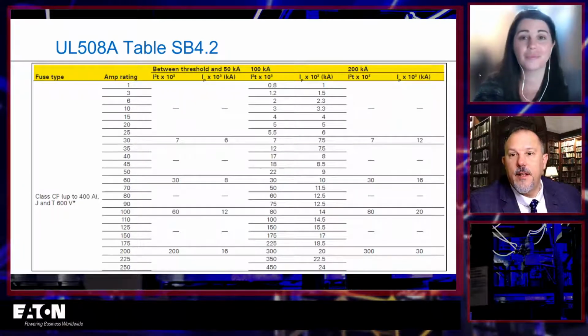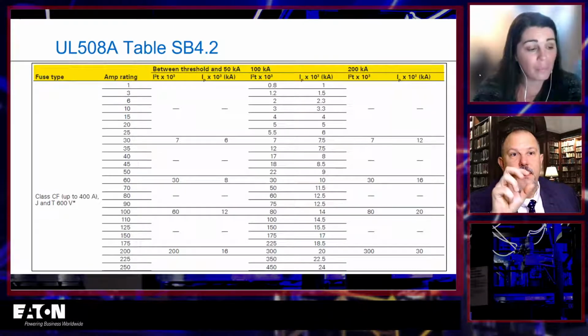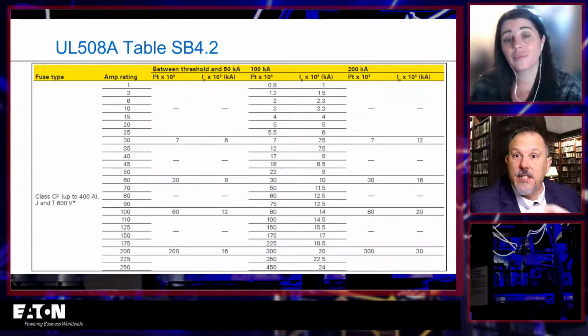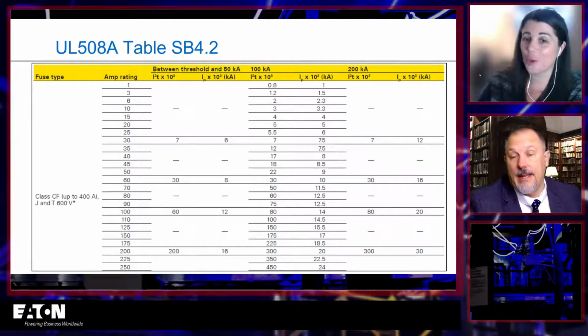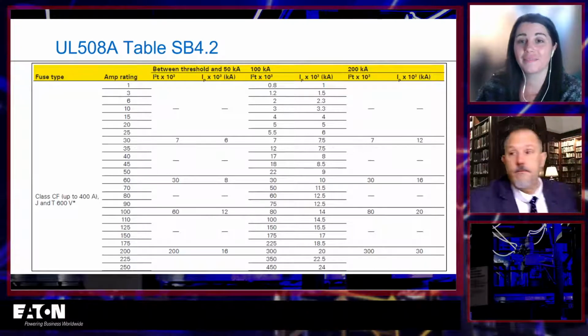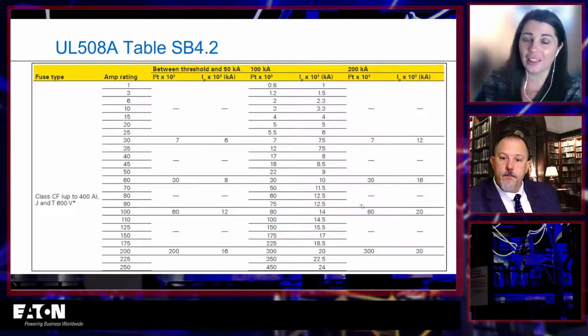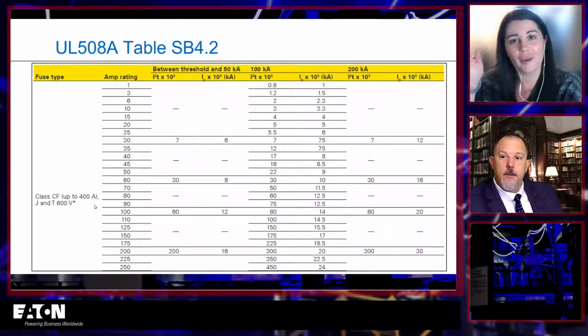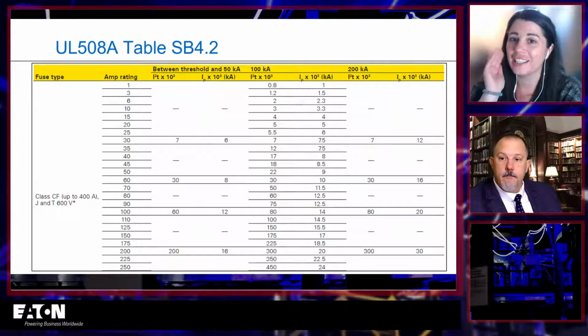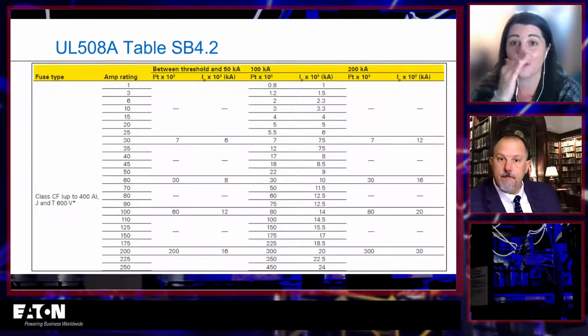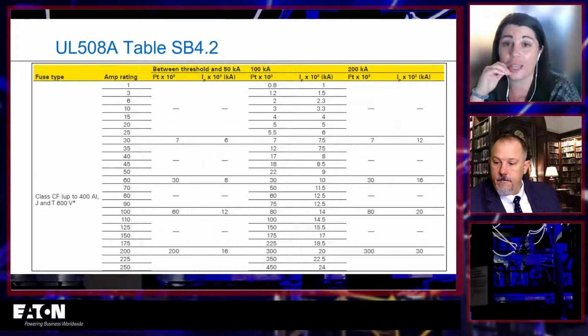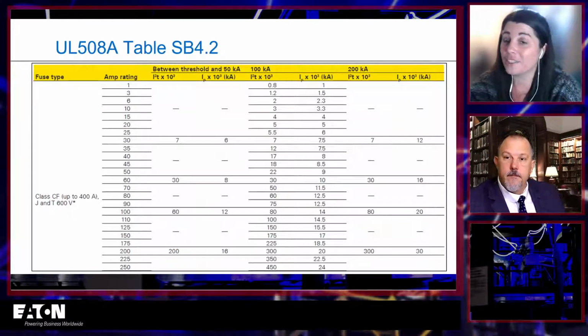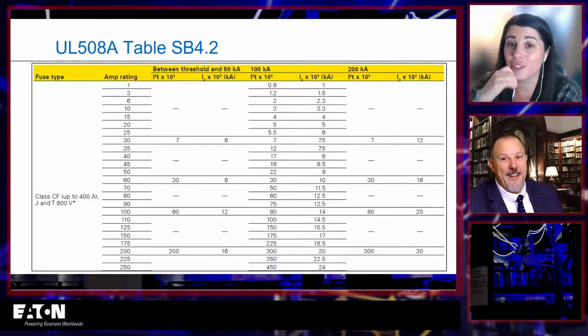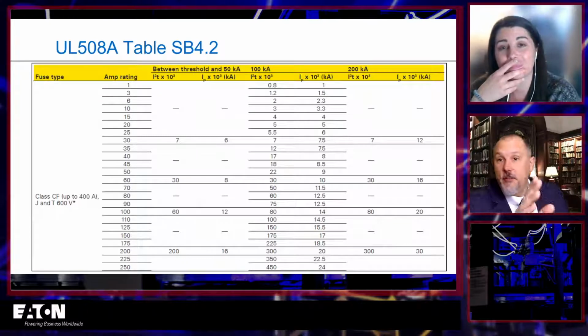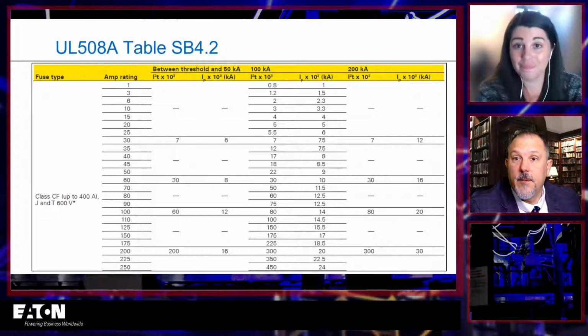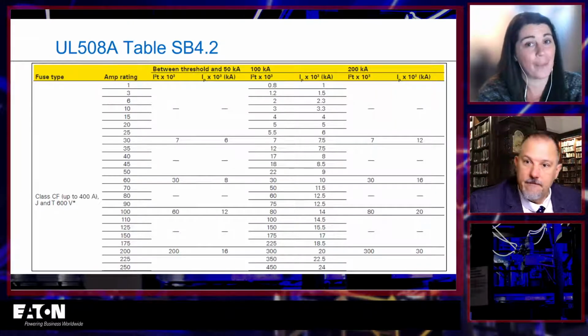And I think another good observation there is that just because you have a circuit breaker in there rated for 10K does not mean the short circuit current rating of that equipment is 10K. Correct. Good point. I know that question comes up every single time, and I wish I had a more concise answer for you, but unfortunately the answer is very complicated, and there are so many factors that go into whether or not you can, or whether your AHJ will accept it too. Half the time that's the determining factor, and some of them just say no. That's true. And then you may have to get a field evaluation from a nationally recognized testing laboratory that looks at these things. Yep.